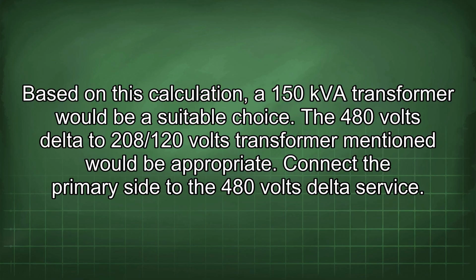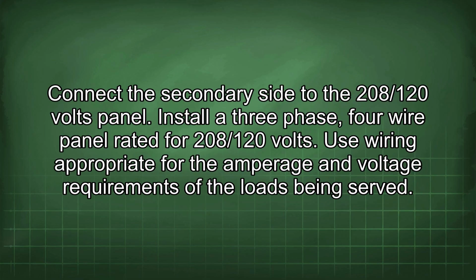Connect the primary side to the 480 volts delta service. Connect the secondary side to the 208/120 volts panel. Install a 3-phase 4-wire panel rated for 208/120 volts. Use wiring appropriate for the amperage and voltage requirements of the loads being served.